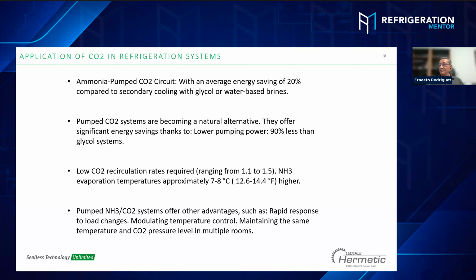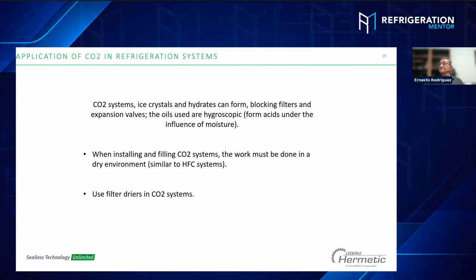Basically, we want to keep it very low for CO2 to prevent flashing, and the design of the coils is already the best way to run the pumps. Also, the advantage of the CO2 pump is that it responds much faster to load changes for any application in the system. We need to use a filter dryer for CO2 pumps. For the CO2 system, moisture is the big problem, not oil. In ammonia it is the oil, and in CO2 it is the moisture, the water.